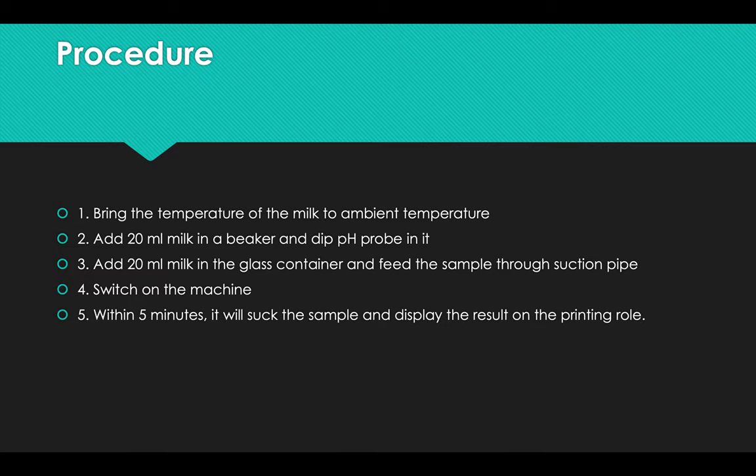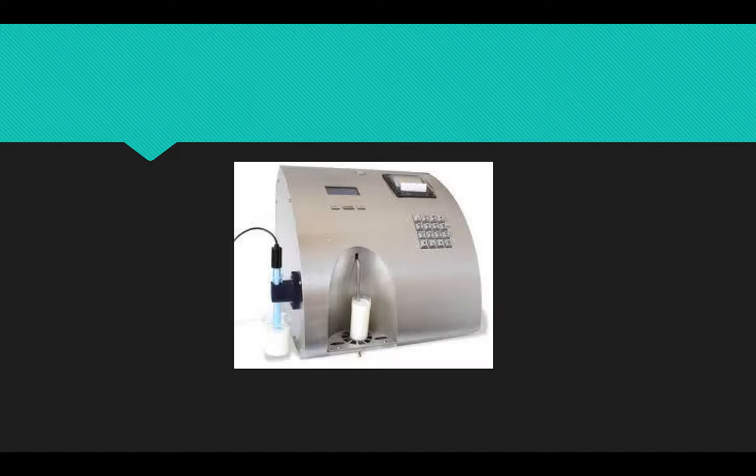Bring the temperature of the milk to ambient temperature. Add 20 ml of the milk in a beaker and dip the pH probe in it. Add 20 ml of milk in the glass container and feed the sample through the suction pipe, then switch on the machine. Within five minutes, it will suck the sample and display the result on the printing roll. This is a simple design of the Milkoscan or Lactoscan.